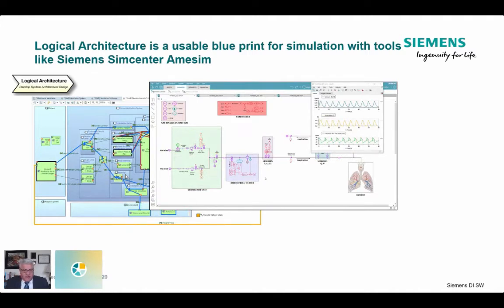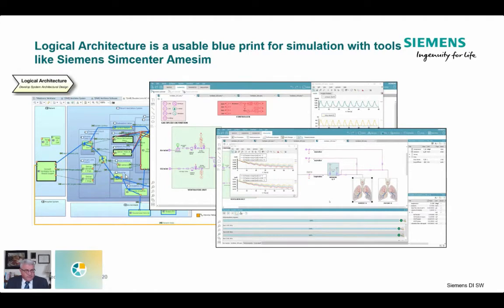Working with our team that uses a Simcenter product — Amesim — they were able to start developing models. They had models already of lungs, patients, and patient systems, but they didn't have one that matched the architecture of this product. By looking at the architectural diagrams I was producing in Capella, they were able to align their simulations to those diagrams. They noticed that air is coming from a regular environment, not a pressurized source, and that a micro turbine was being used rather than bellows to represent the design. They were then able to build an accurate simulation that mapped to the design.